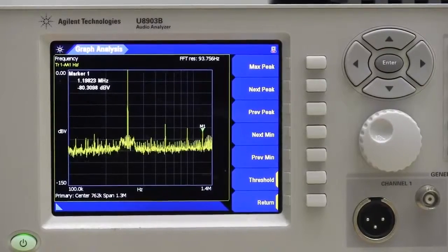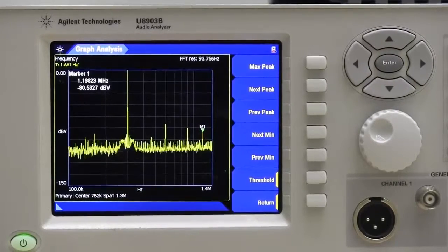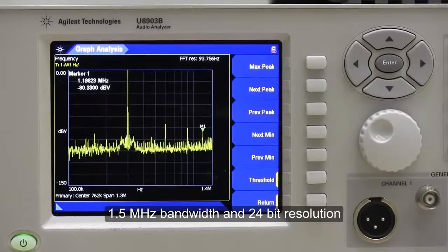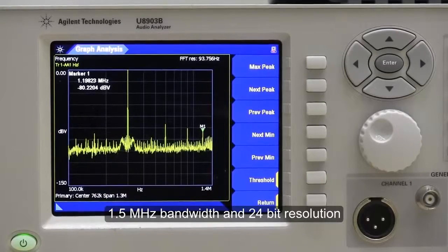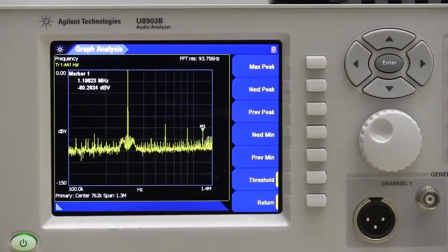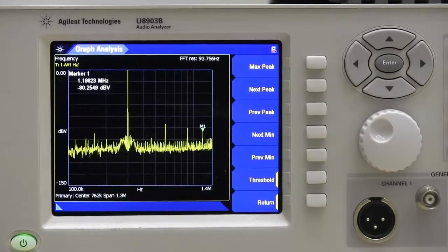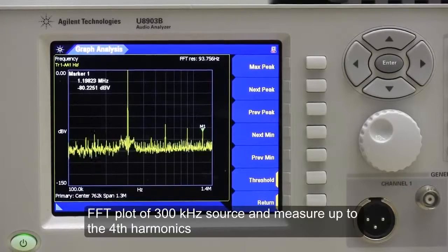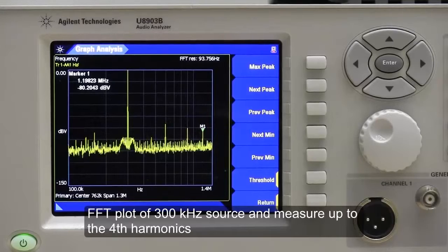For component and IC testing, the U8903B comes with a wide bandwidth option, expanding the upper limit of the measurement bandwidth to 1.5 MHz with 24-bit resolution and a 1 million point FFT. This expanded bandwidth allows the audio analyzer to maintain high accuracy even when monitoring Class-D amplifiers or switching supplies, which often produce signal spikes far outside the bandwidth limit of conventional audio analyzers — typically at 100 kHz or less. This screenshot shows an FFT plot of a 300 kHz source and the U8903B's unique ability to measure up to the 4th harmonic.